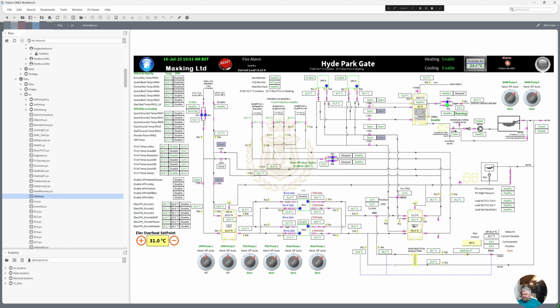It's pointless getting rid of it into this tank because this tank feeds for the underfloor heating and the manifolds, and we've got that off. There's no underfloor required. We want chilled. And then these two gas boilers up here, they are feeding the domestic hot water system. They can also feed this buffer tank if they choose, but we don't ever feed it. So this valve here is bypassing all the way back, this CV13. So we're never feeding this tank.